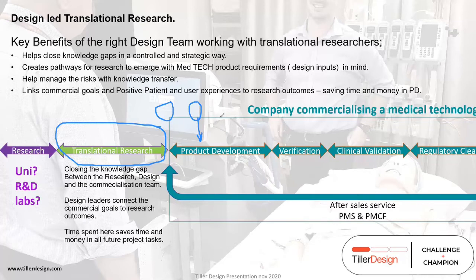Technical triggers switch documents from draft to controlled as soon as we want to publish anything for any form of review. Even back in research, we'll design test jigs, and in the case of mVision we designed and fabricated the antenna arrays in the headset scanner because the university could only simulate. We stepped in early and helped realize a simulated environment into a real-world and then a product environment. Our team starts the medical device design process straight away, but won't formalize a controlled document until the very first review.